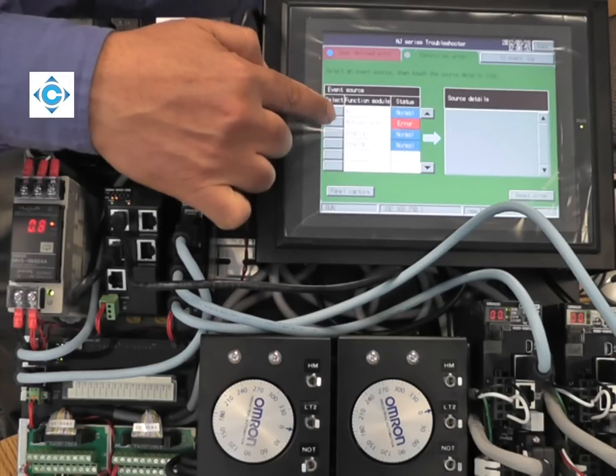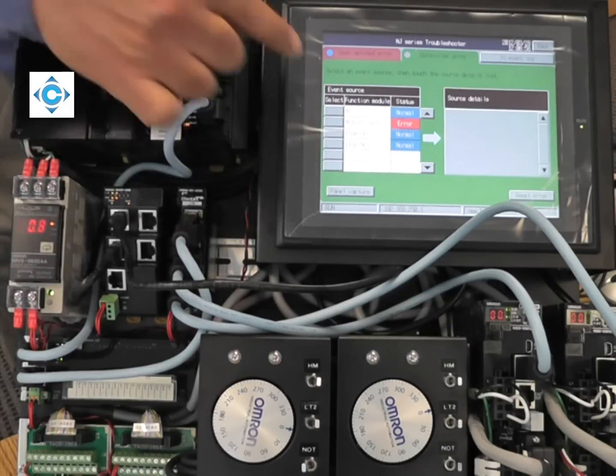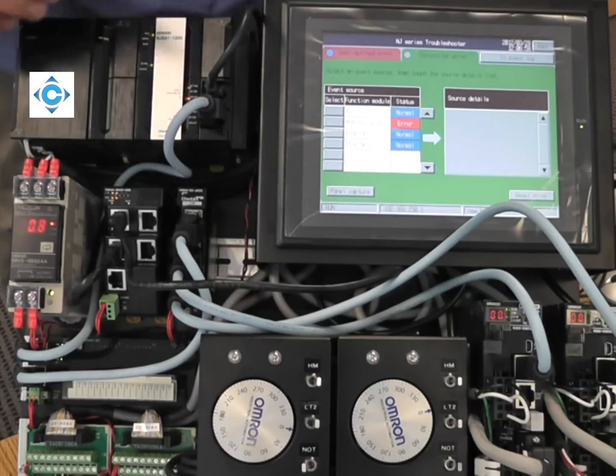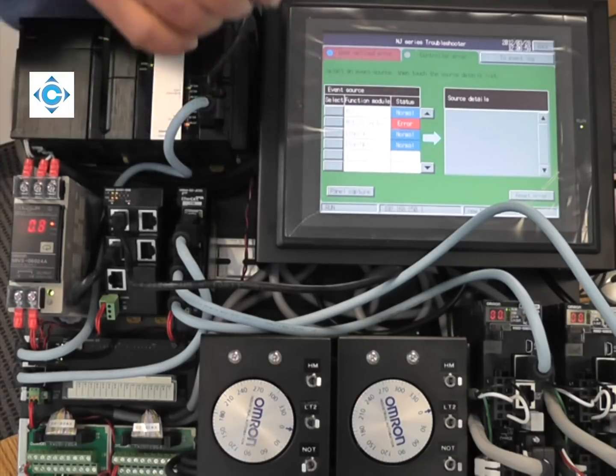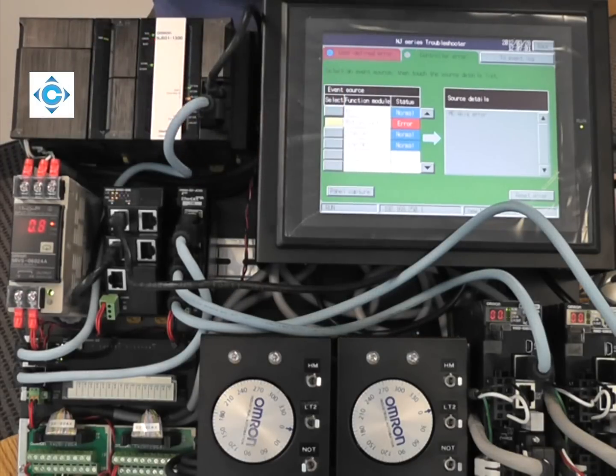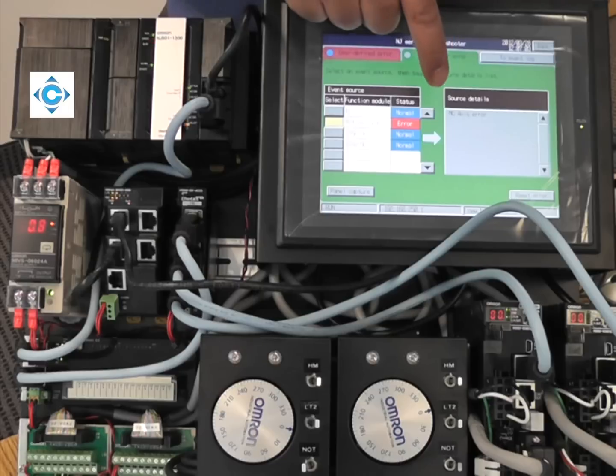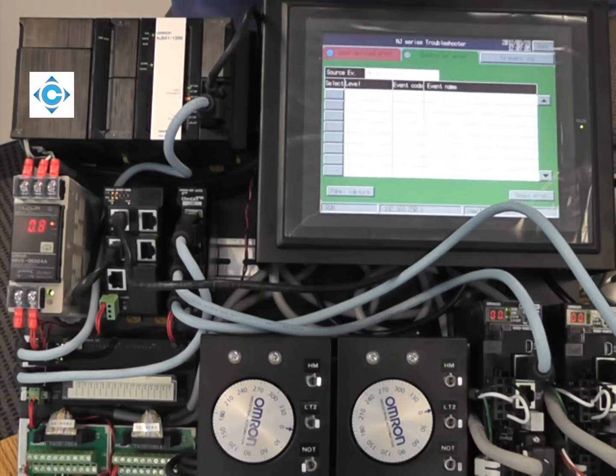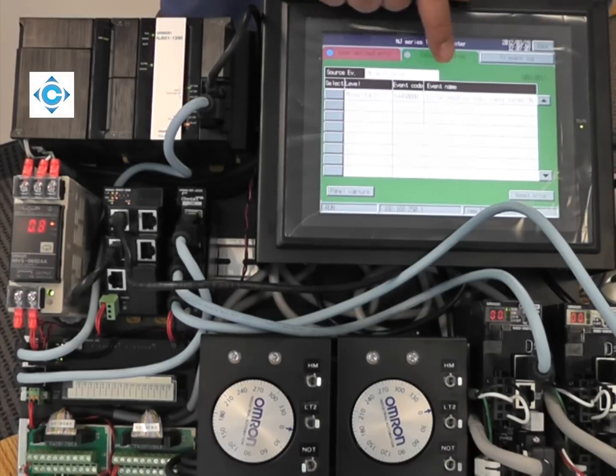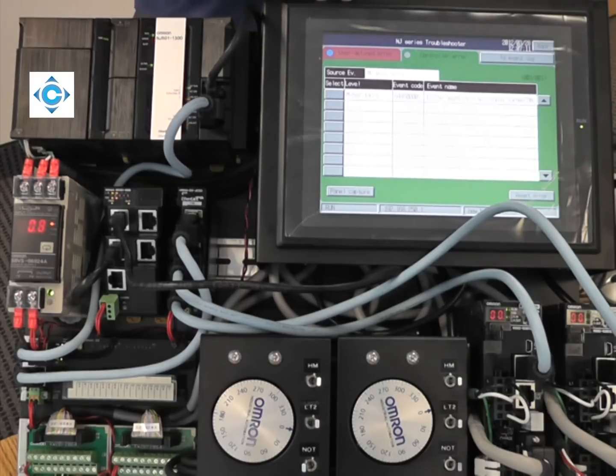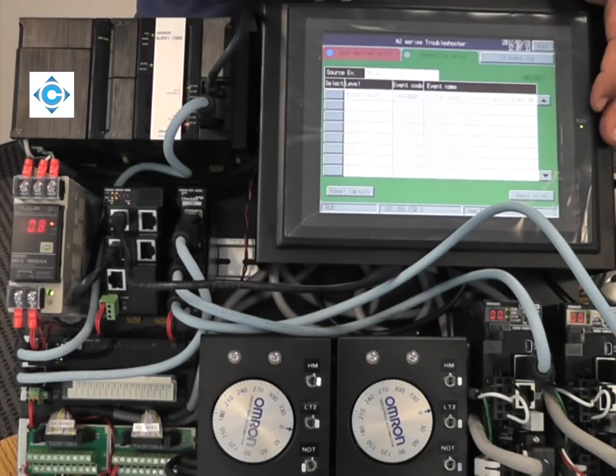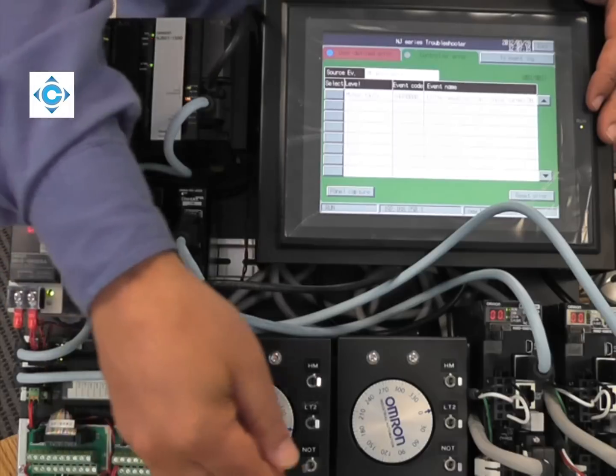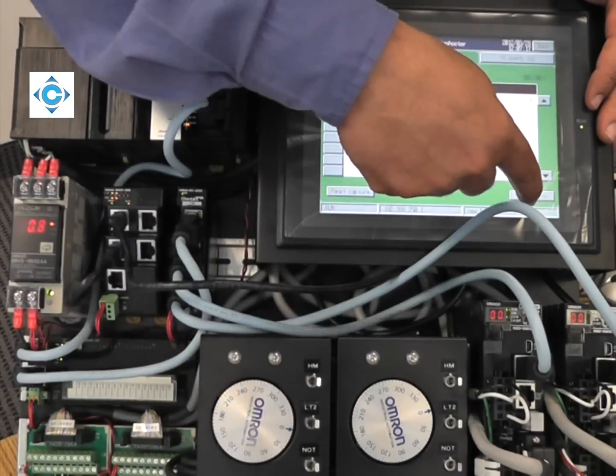The one with the motion has red on it. If I click on the motion, it's telling me that you have an axis error. Then I go to the axis, and it's the exact error I caused: negative input over-travel on this servo. You can clear it from here.